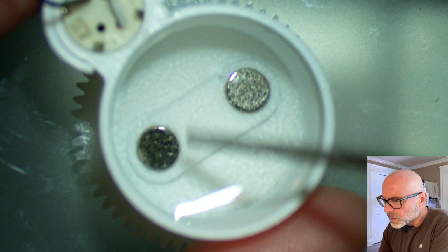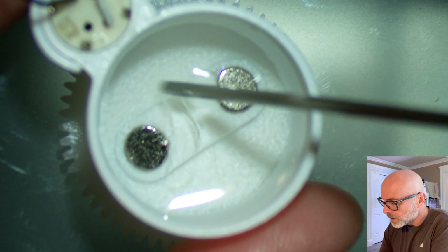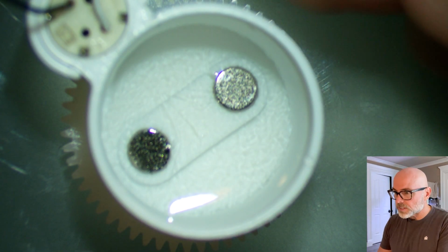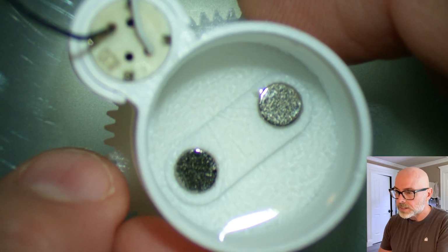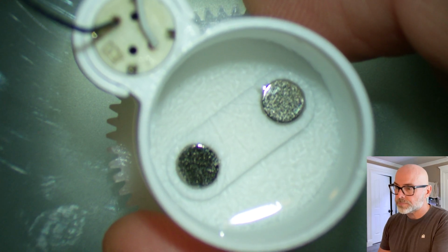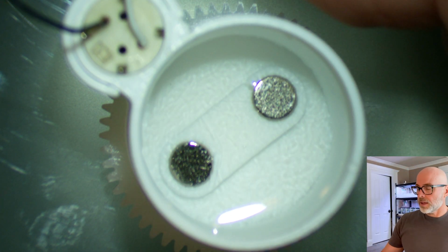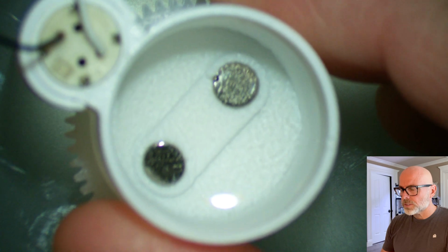I'll just move it around a little bit, and you can see the swirliness. That is, it's not well mixed. Now I'll turn on this little motor. It has a little pinion and then a spur gear. The spur gear has two magnets on the bottom of it. Then there's a little mixing bar with magnets that match the magnets on the spur gear below. As we turn it on, here we go, it's starting to spin up.